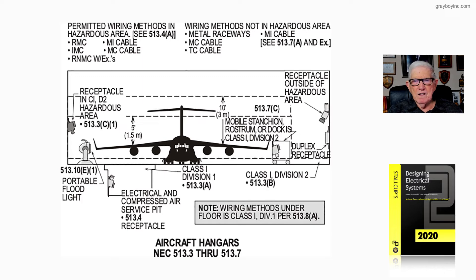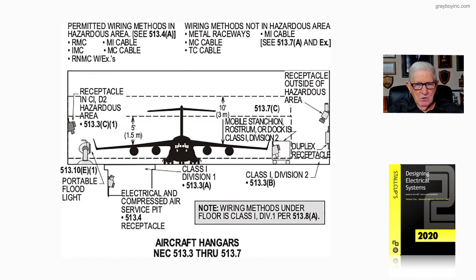A Class 1 Division 1 area is in the pit and also in the concrete. If you're an electrician running wiring in that concrete, you're in a Class 1 Division 1 area and must use wiring methods permitted under 501.10a. When you come out of that concrete and emerge, within 18 inches you're going to need a seal — that seal is required.